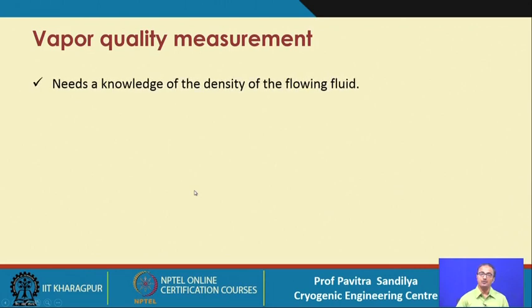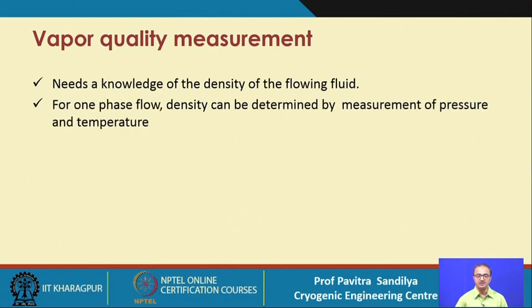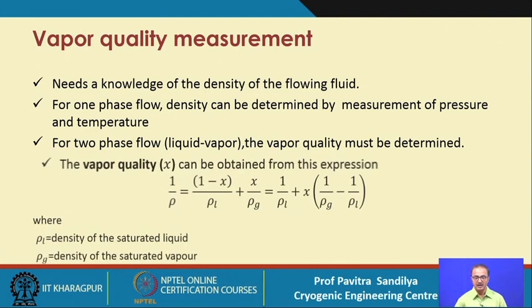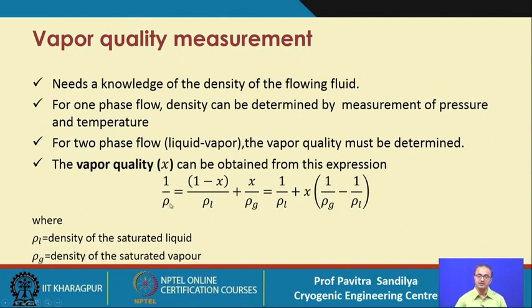Vapor quality is determined using the density of the flowing fluid. For single phase flow, density can be calculated from pressure and temperature using an equation of state. For two-phase flow, density is found by knowing the quality, using the expression: density of two-phase mixture correlated with quality x, where x is the vapor fraction (amount of vapor per unit mixture) and (1−x) is the liquid fraction — combining liquid density and vapor density accordingly.